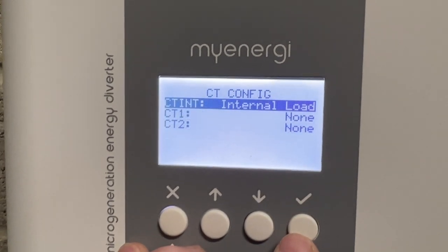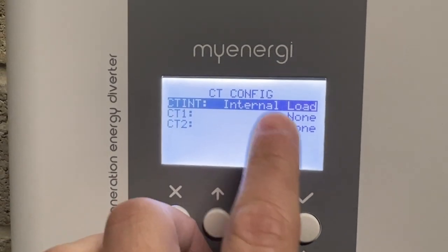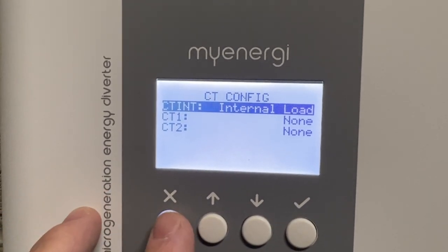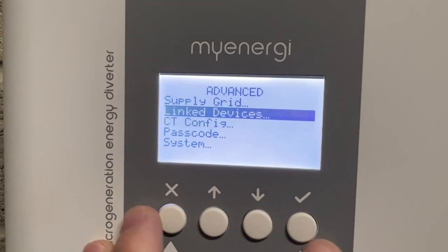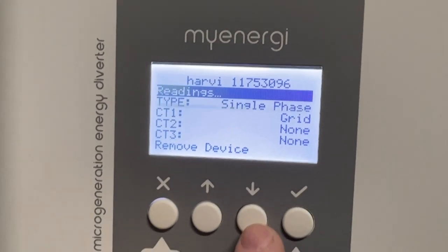It's very important: if it's external, then the internal CT has to be disabled, otherwise it will conflict with the primary and ignore the harvi. Once that is disabled, go to Linked Devices, go to Devices, find the harvi, and check the serial number matches your harvi.